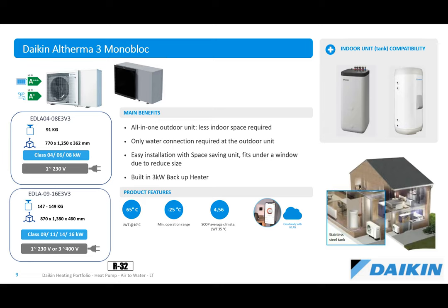So this time of the year specifically, if you're turning on a heat pump for the first time, the water in the system must be above, I think it's 12 degrees. So the compressor will not run until the water temperature flowing around in the system is above 12 degrees. And the backup heater assists in allowing that to come up to temperature rather than waiting, because obviously the water temperature this time of the year is very cold. So that's the monoblocks. They're ideal for retrofit scenarios because you're not having to fit in any unusual size indoor unit in a space that you don't have available.